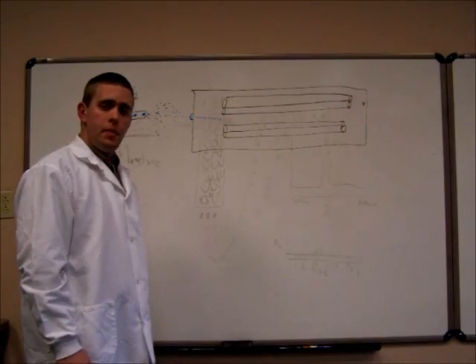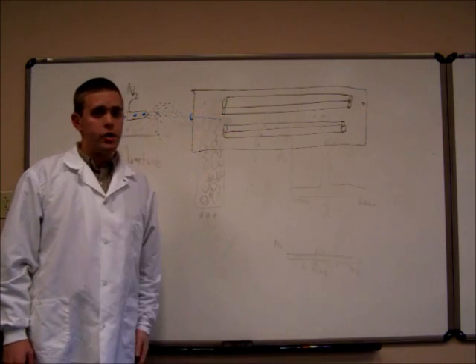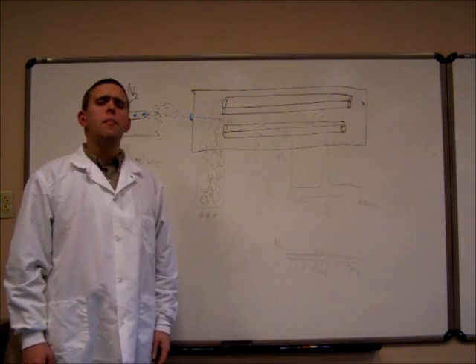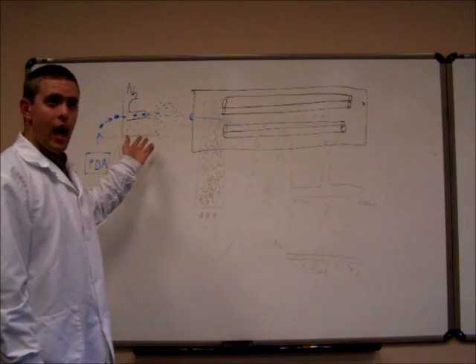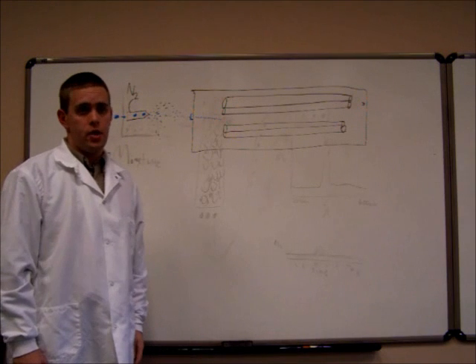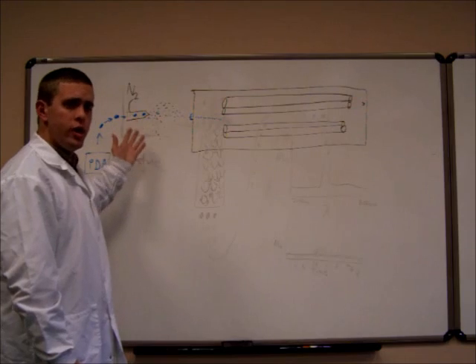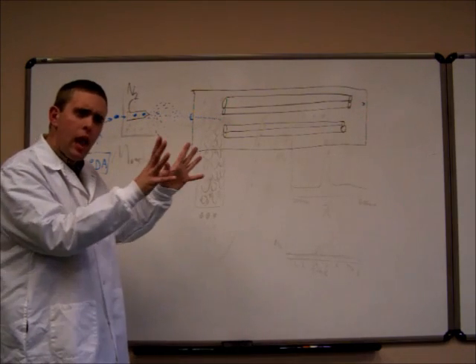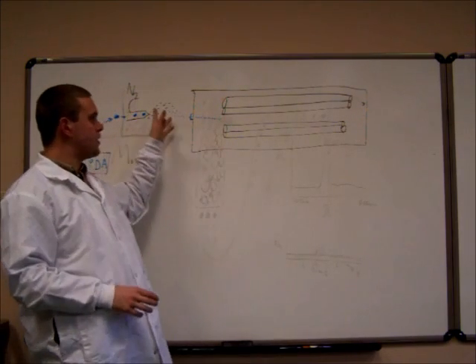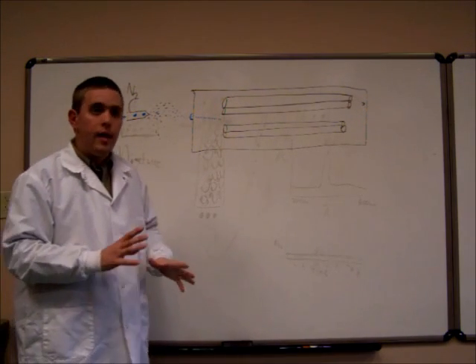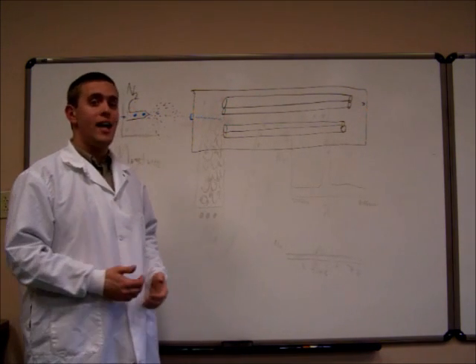After being analyzed in the PDA, the analyte travels through the tubing to the mass spectrometer. In the mass spectrometer, the first thing that they interact with is the ESI, or the electrospray ionizer. The electrospray ionizer uses a nebulizing gas, which is usually nitrogen, to nebulize the analyte, or create a fine mist. In the process of creating this fine mist, the analyte becomes ionized with either a positive or a negative charge.